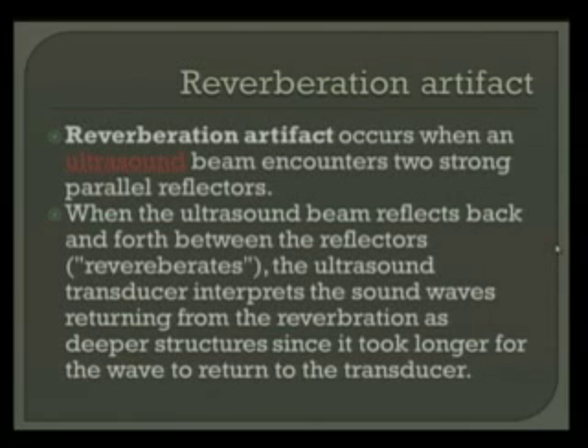Reverberation artifact occurs when an ultrasound beam encounters two strong parallel reflectors, right? The ultrasound beam is seen between those two. When the beam reflects back and forth between the reflectors, that is causing reverberation. The ultrasound transducer interprets the sound waves returning from the reverberation as deeper structures, since it took longer for the wave to return to the transducer. So basically, let's say there are two reflectors, maybe one is a diaphragm and one is the lung. Gas, for example, over here will give us some reverberation artifact. It'll oscillate between the diaphragm and the lung, that gas. And when it's finally done reverberating and returns to the transducer, the transducer thinks, oh my God, this took like 3 milliseconds to return to me, so it must be a deeper structure.